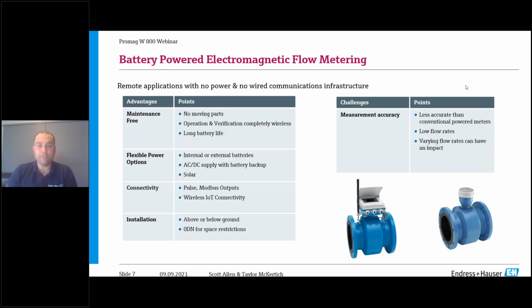So with flows where you might have fluctuation, and you're only sampling every 15 seconds, there's potential to miss those fluctuating flow rates, which can cause inaccuracy. We have some availability and functionality I can share later on how we can potentially overcome that. Being an electromagnetic flow meter, another aspect that can affect accuracy is flow velocity—we need a certain flow velocity for accurate and repeatable measurement. So that's another factor to keep in mind with your flow metering.